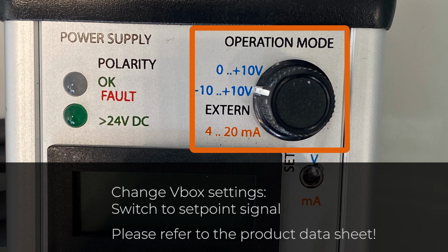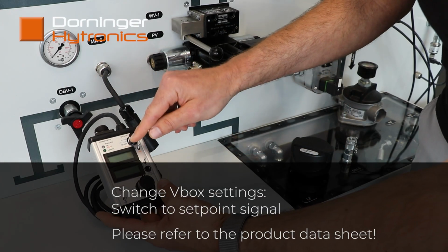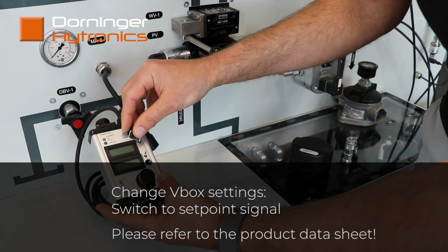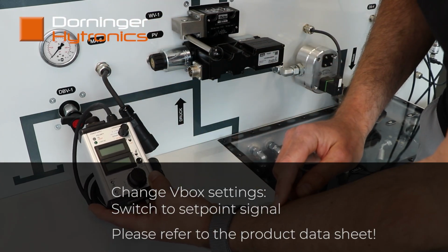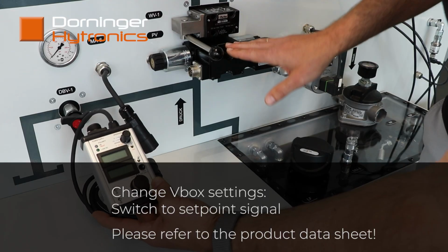To do this, we change the Vbox settings. The Vbox must now be switched to setpoint signal output. Here again, the settings must be selected in accordance with the information in the product data sheet. The Vbox is now no longer used to measure the control signal. Instead, it actively controls the control valve. This allows the valve to be tested independently of the machine control system.